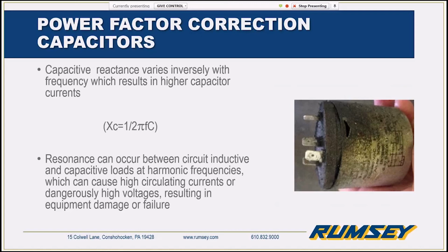So like all capacitors, they are basically a well for that harmonic distortion to fall into. They'll keep calling for more and more of it, and more harmonics will go to them until they become less effective and fail. So it's always something to keep in mind, because power factor correction capacitors are a great tool to use whenever you are trying to correct for linear loads, but you'll just want to make sure you have something in between any VFD loads and these power factor correction capacitors. That'll help to protect them, so that, for example, we could do what we're best designed for, correcting for that harmonic distortion, and then they can correct very cost effectively for the power factor for any other linear loads that are in the system.